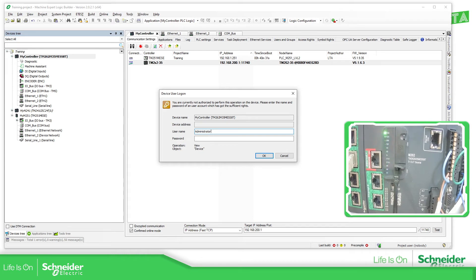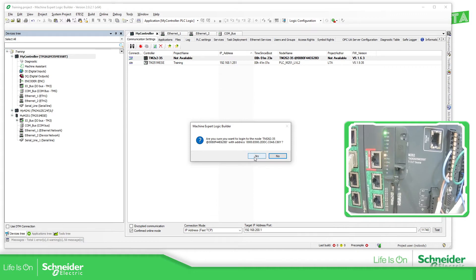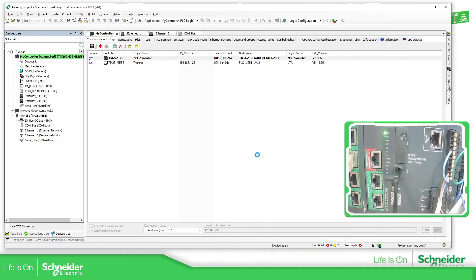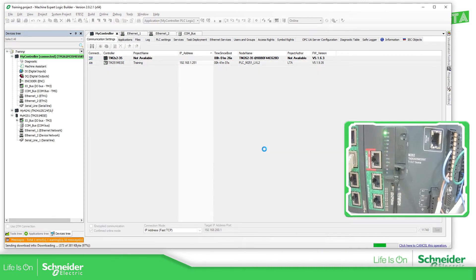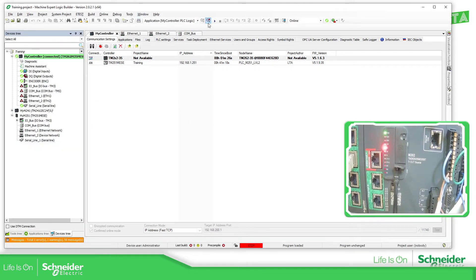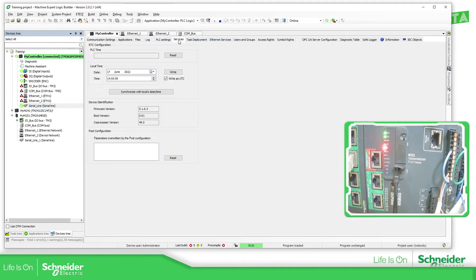So now I need to log in — Administrator, administrator. This should be the behavior you may have on your controller. The only difference will be the credentials. Now it's downloaded the application and the application is already on the controller — you can see it just in run. You can see all the diagnostics of the Ethernet port and everything. The main thing you need to do is go to Service, read the actual time of the controller, and if it's different, synchronize with local time or write the new value that you want.